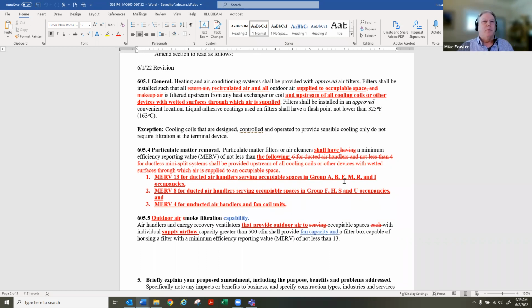And so now I counted up this morning, we had 7 rounds of review with Eric over the past few weeks. This proposal now contains in 605.1 some clearer language on the filtered air. And it also brings the language from 605.4 on cooling into this section. So the language on filtration being upstream of any heating or cooling is now within 605.1. 605.4 lists out the MERV level of filtration for specific occupancies, and in trying to clean it up, fan coils were proving the most difficult. Fan coils are included in the unducted air handlers. And then there are a few suggested edits to the language that was previously approved by the TAG in 605.5. The blue is language that the TAG previously approved, and the red is some proposed new edits. So that's the quick summary.